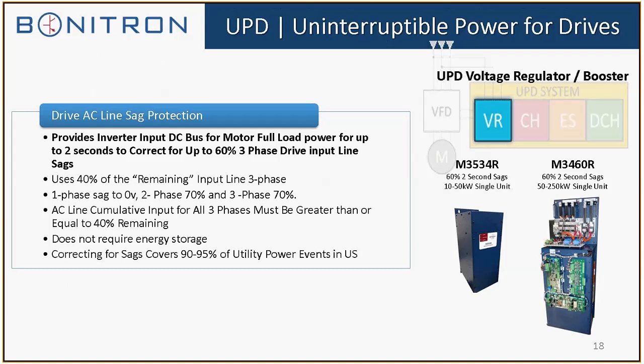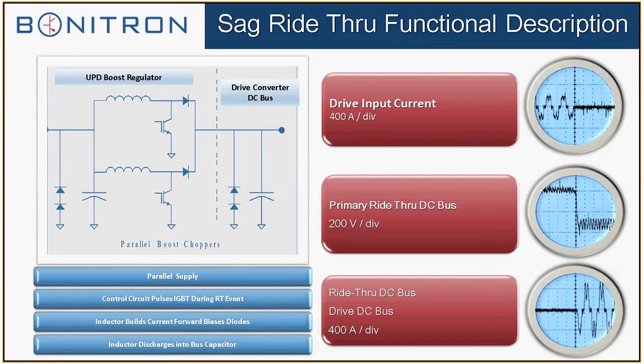I think we've pretty much covered this already, but over on the right you see the two versions of the modules, the 3534. They both do 60% 2-second sags, 10 to 50 kilowatts in a single unit, 50 up to 250, and we can master-slave the 3460s. Now, ride-through function. This represents the internal circuitry, or the boost circuitry, for the ride-through. It's parallel to the bus, as we said, but also internal to the ride-through. If you get up above 50 kilowatts in the 3460s, it will have a secondary stage, or it will go in stages of 50 kilowatts. So if you were to lose a stage, you'd still have 50 kilowatts of ride-through left, and it would be the same amount of time. That would be in a 100 kilowatt unit, and respectively on up. You can lose one phase and the ride-through will still function.